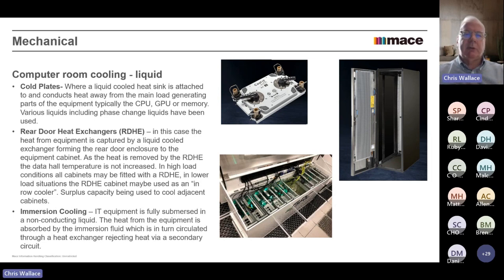The next one is perhaps a little bit more conventional: rear door heat exchangers. I think this is probably a very useful halfway house at the moment. Here you have a big coil on the back of the equipment cabinet. You reject the heat through the equipment cabinet as you would before, but this time, before it gets blown into the hot aisle, because in this case you wouldn't have a hot aisle per se, you would have this big finned coil, and you'd run some liquid through that and remove the heat coming off the equipment in that liquid. This may or may not have fans in it, and you can use different fluids again. Quite often what you'll do is run a return pair using cool water rather than chilled water above the cabinets and drop off to these doors.